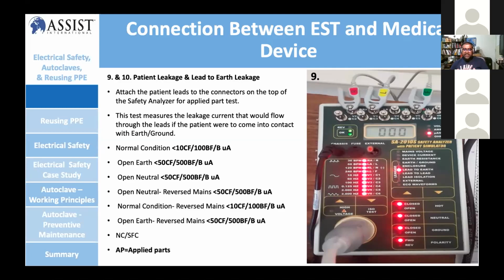So for patient leakage current, lead to earth, you are measuring the lead referring to the earth. So when you are measuring lead to earth, you are checking the leakage between the lead and the earth. In normal condition, it should be below 10 for CF, and BF 100 and B as well. Open earth should be below 50 for CF and 500 for BF and B. Open neutral, same thing, 50 for CF and 500 for BF and B. So these are the standard readings according to IEC 60601 and 62353.